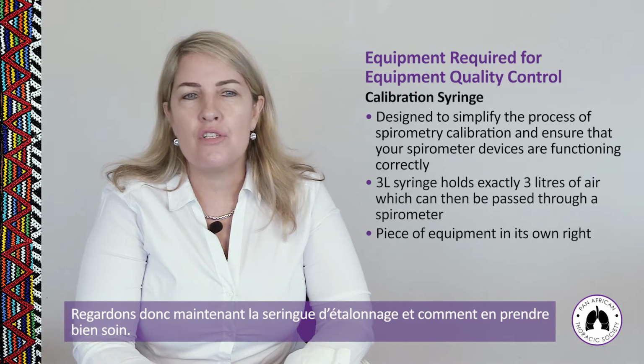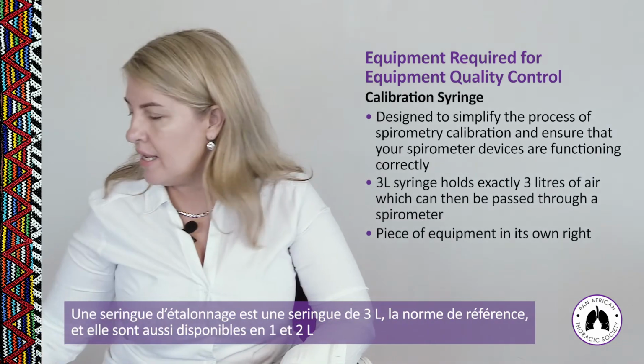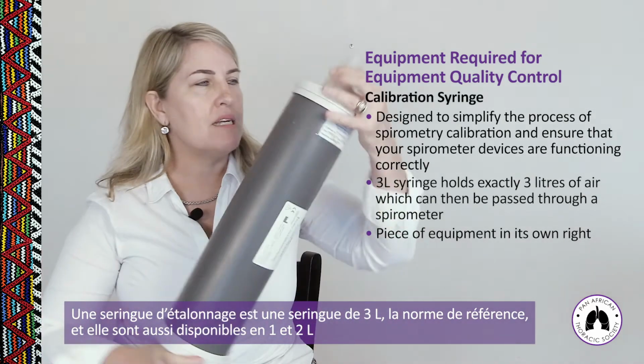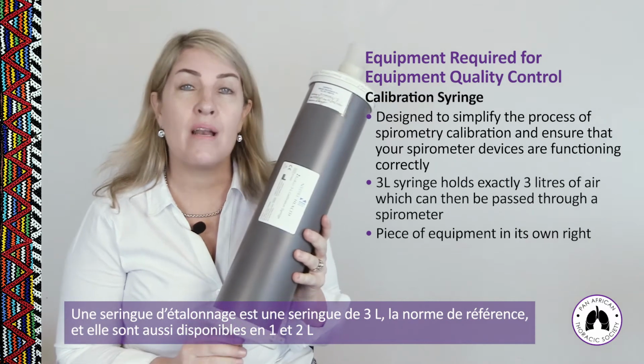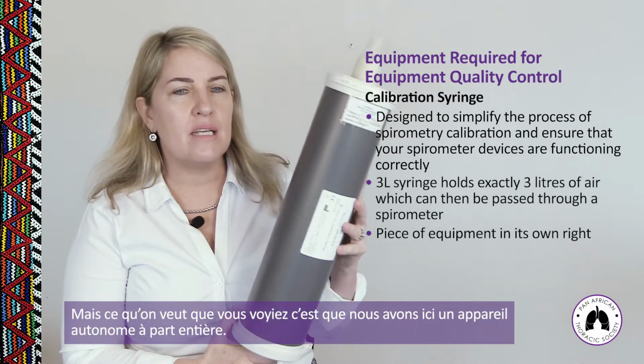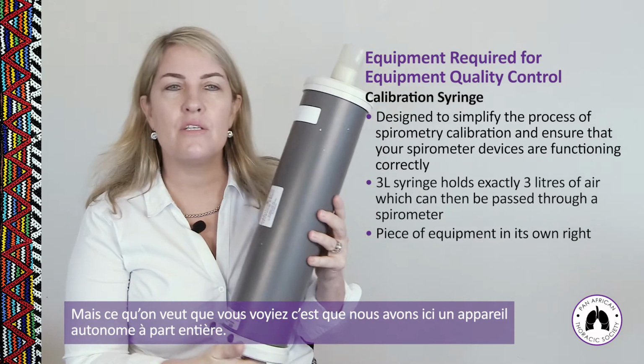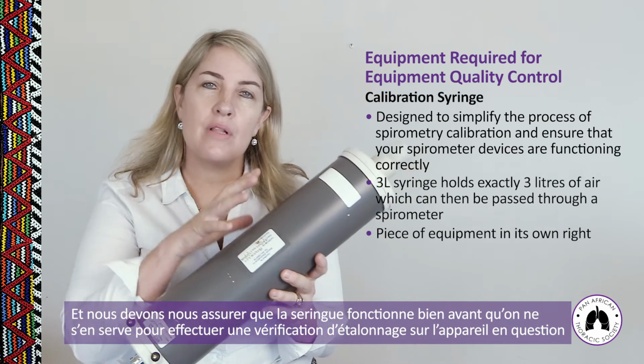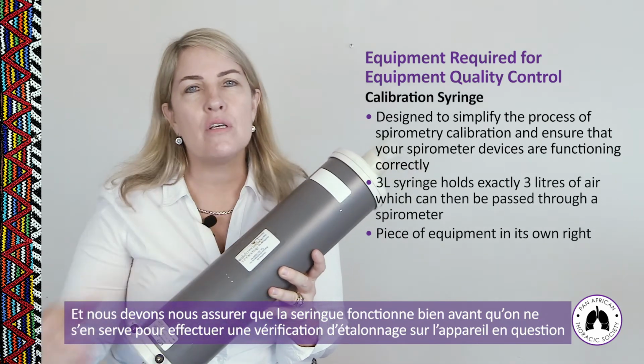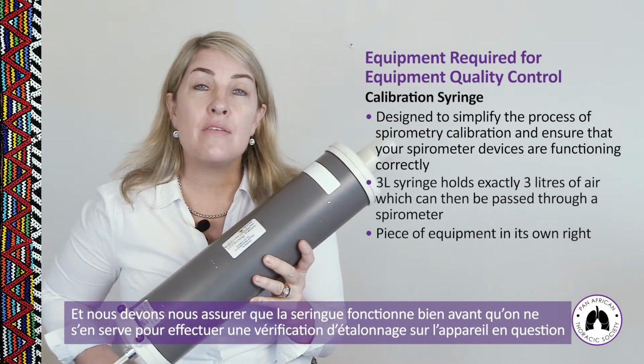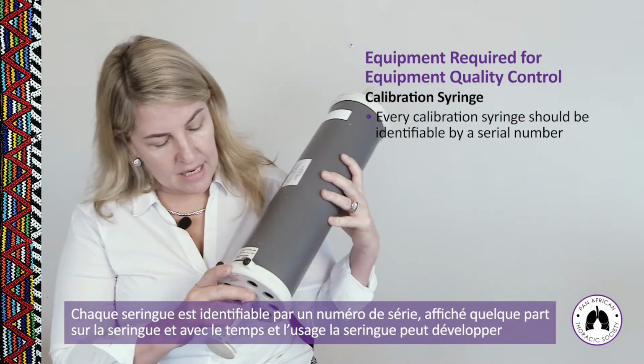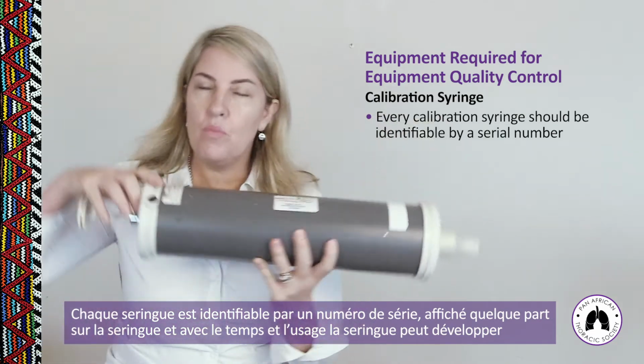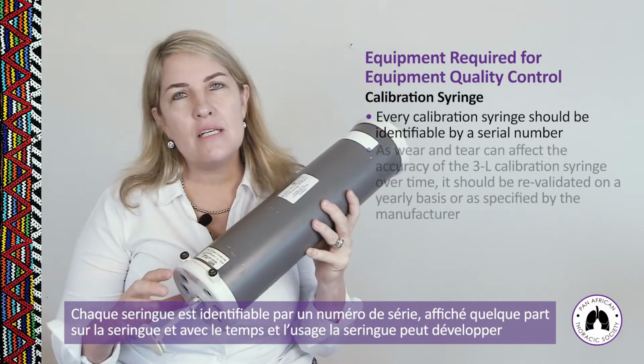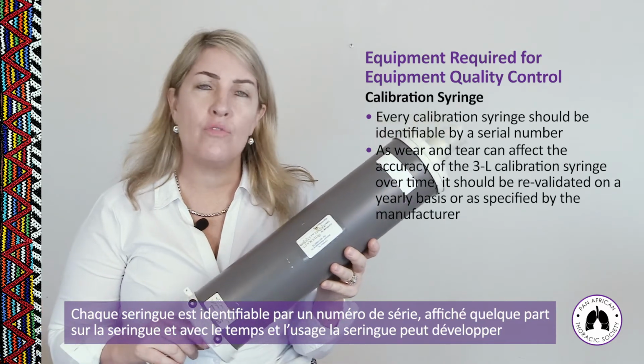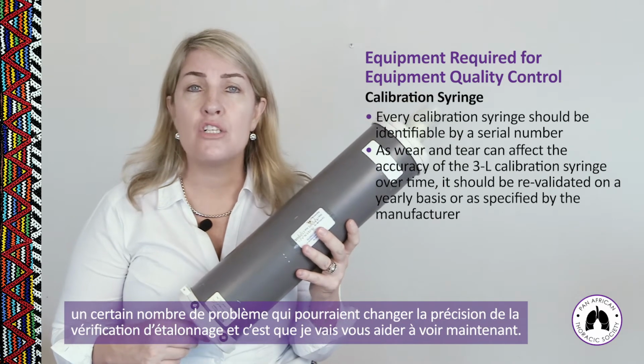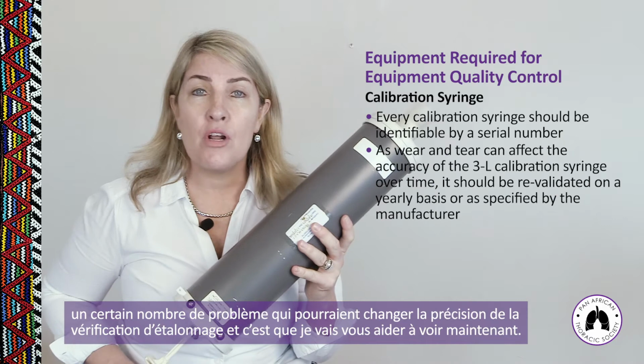Right, let's look at our calibration syringe and how to care for the calibration syringe. So a calibration syringe is a 3-liter syringe, which is the gold standard. They do come in 1 and 2 liters as well. But really what we're wanting here is for you to understand that this is a piece of equipment in its own right, and that we need to make sure that this syringe is in good working order before we use it to actually conduct a calibration check on the device itself. Every calibration syringe is identifiable by a serial number, which can be found on the syringe somewhere. And over time, wear and tear can cause this syringe to have various issues which could change the performance of the calibration check. And that's what I'm going to help you to look at now.